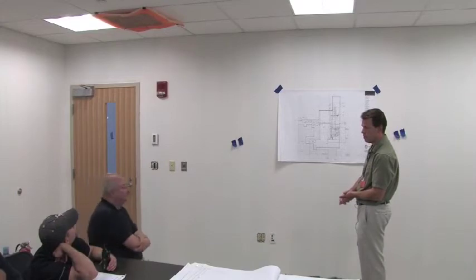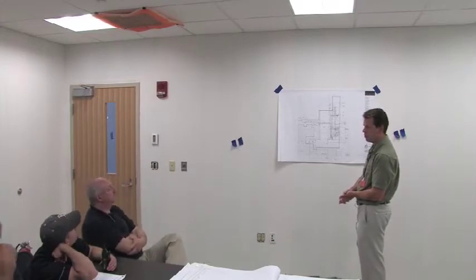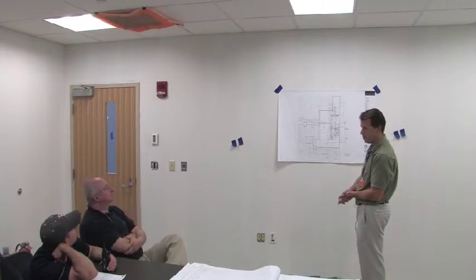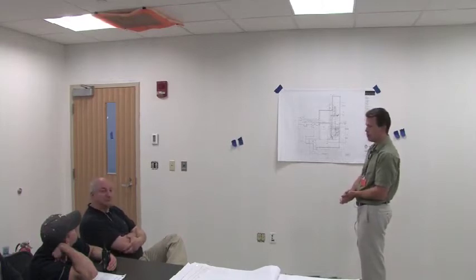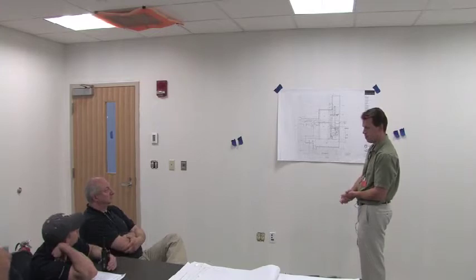So just help me understand one more time, because you got 2 things up there, low zone and high zone connections. Correct. Is that to feed the fire pump, or is that to feed the fire department water? Is that for water to be fed to us? That's for water to be fed to you. To us? If the fire department needs to add water to your system, they will connect. So if they say, we have a fire and we need to add water, and it's the lower part of the building, they're going to connect to the low side, and that's going to go up and feed 5, or 4 and below, correct. If they know there's a fire in 6 and above, they're going to go to the high side, hook up to that and feed water to the high. Exactly.